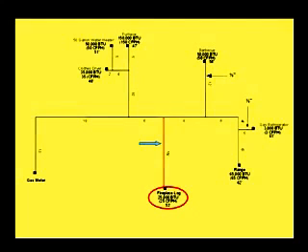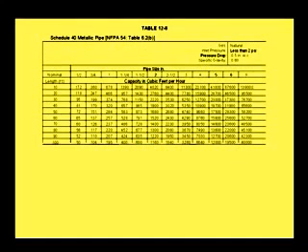The 15-foot section that supplies gas to the fireplace log has a demand of 25 cubic feet per hour and is 53 feet from the meter. Refer to table 12-8, 60-foot row — 25 will fit under 65 — and see that a 1/2-inch pipe will accommodate the 25 cubic feet per hour demand for the fireplace log.